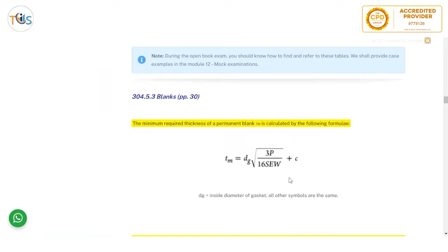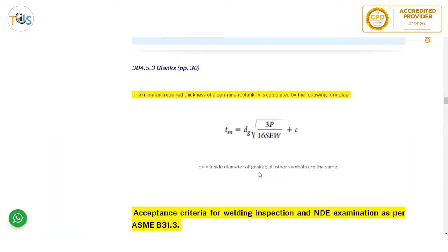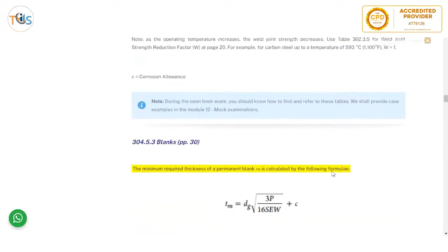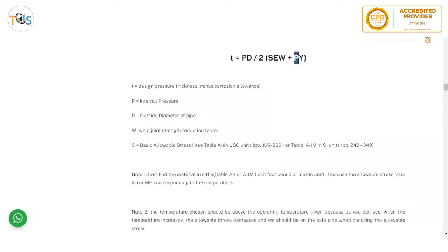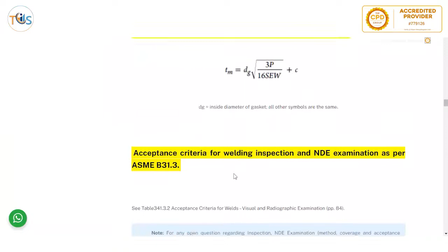Okay, so for pipe blanks, you go to page 30, and you have this formula. The minimum required thickness for permanent blank is calculated by this, and everything is the same except the dg, which is a new parameter, the inside diameter of gasket. All other symbols are the same as the formula we have shown here at the top. So internal pressure, outside diameter, and the allowable stress, and joint efficiency and weld efficiency, etc. Okay, plus C, which is for corrosion allowance.